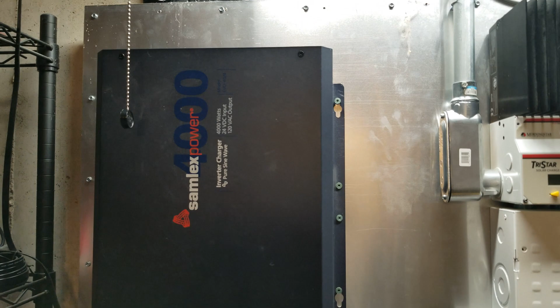One other thing from Battle Born: they also recommend, if you have a 4,000 watt inverter or higher, which I do, that you get this current surge limiter. I don't think I've seen anybody have this, even though they have some large inverters, but I went ahead and bought it just to stay in compliance, just in case I had any problems with these batteries. There was a learning curve. So what this current surge limiter is, it's a CSL. I think it was the CSL 300 when I bought it, and I think they have a 500 now. The 300 and 500 refers to the amp rating of the device, all the transistors in there and whatnot.